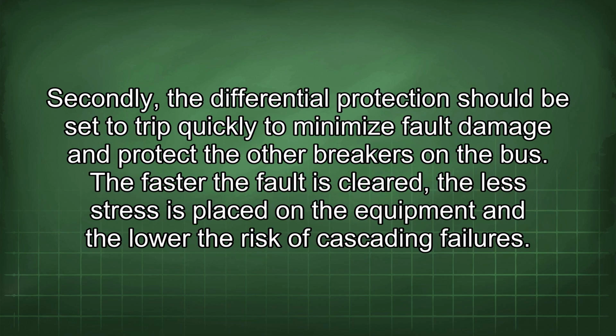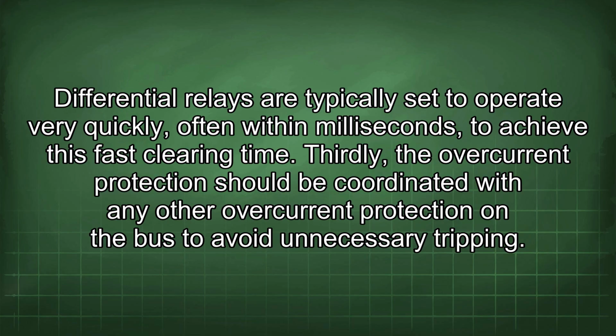Secondly, the differential protection should be set to trip quickly to minimize fault damage and protect the other breakers on the bus. The faster the fault is cleared, the less stress is placed on the equipment and the lower the risk of cascading failures. Differential relays are typically set to operate very quickly, often within milliseconds, to achieve this fast clearing time. Thirdly, the overcurrent protection should be coordinated with any other overcurrent protection on the bus to avoid unnecessary tripping.